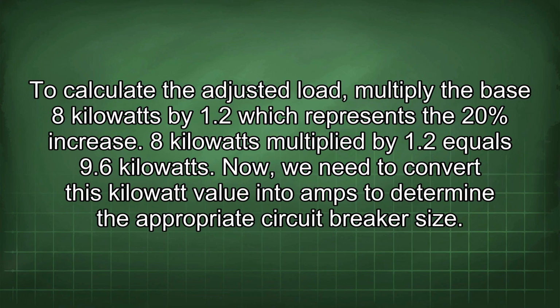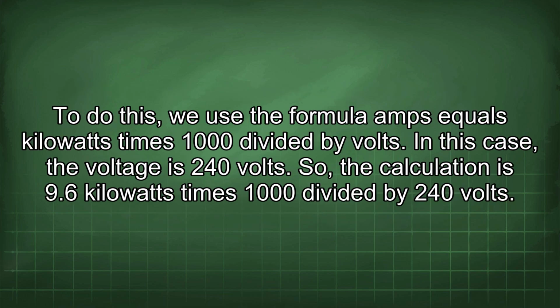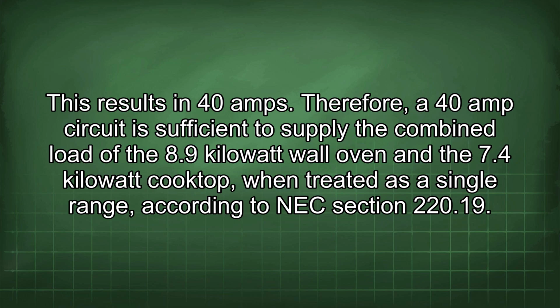To calculate the adjusted load, multiply the base 8 kilowatts by 1.2, which represents the 20% increase. 8 kilowatts multiplied by 1.2 equals 9.6 kilowatts. Now, we need to convert this kilowatt value into amps to determine the appropriate circuit breaker size. To do this, we use the formula amps equals kilowatts times 1000 divided by volts. In this case, the voltage is 240 volts. So, the calculation is 9.6 kilowatts times 1000 divided by 240 volts. This results in 40 amps. Therefore, a 40 amp circuit is sufficient to supply the combined load of the 8.9 kilowatt wall oven and the 7.4 kilowatt cooktop when treated as a single range, according to NEC Section 220.19.